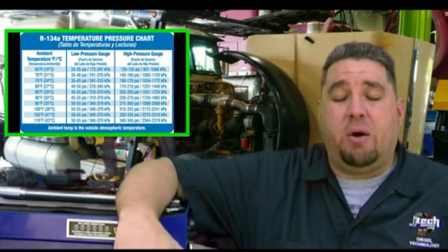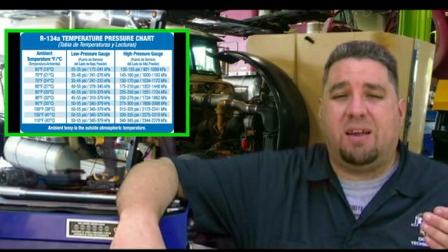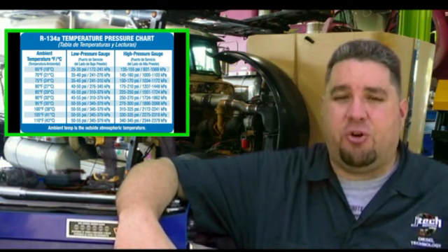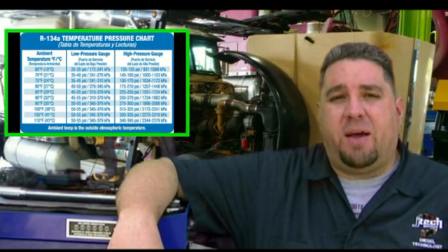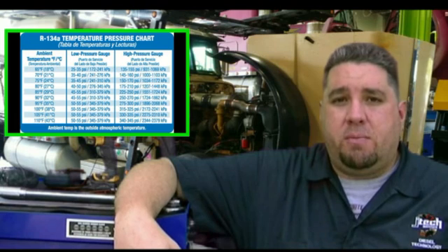The next thing you want to have with you is a temperature pressure chart. This temperature pressure chart is going to give you what your pressure should be on the high and the low at the current ambient temperature. Now, when I say ambient temperature, I mean the temperature immediately in your area. You can check your phone to get that temperature. It's not technically your area, but you want to have a thermometer nearby so that you can get the reading. If you don't, you can go off of the widget on your phone, but you want the current ambient temperature because this is going to affect your pressure readings.